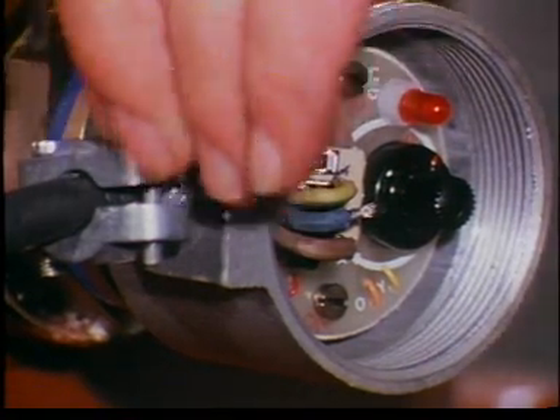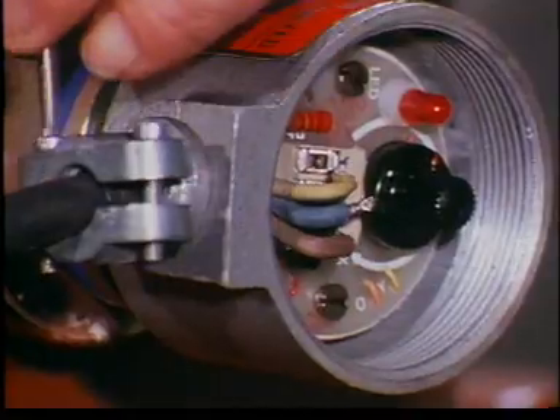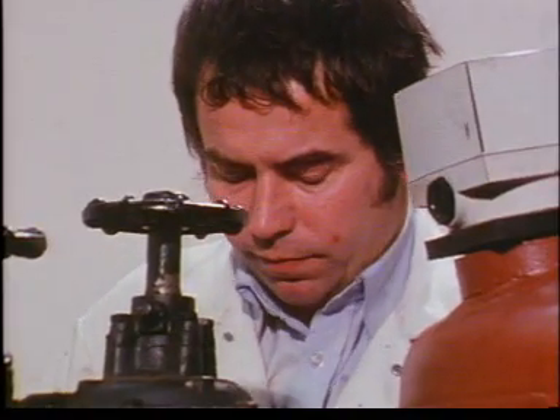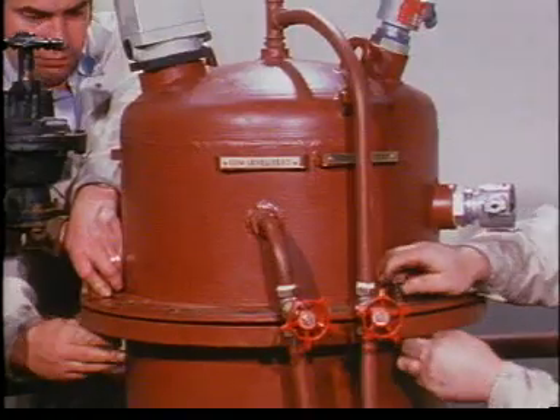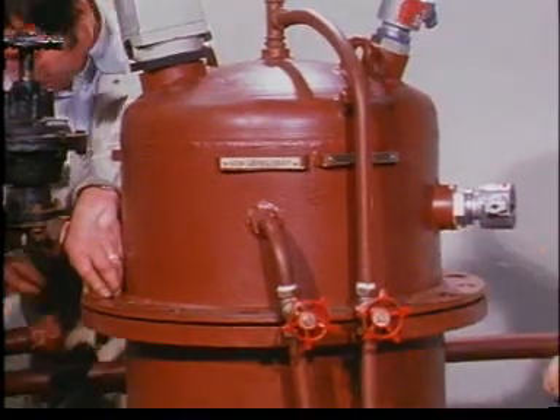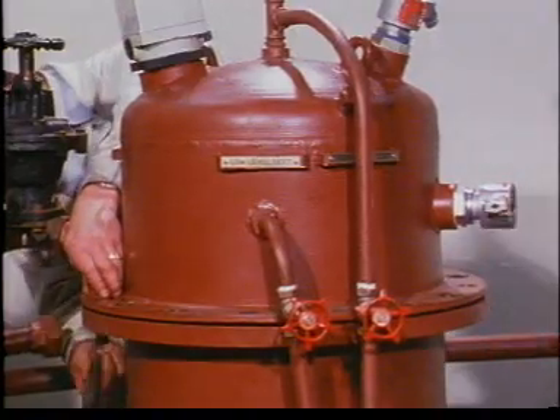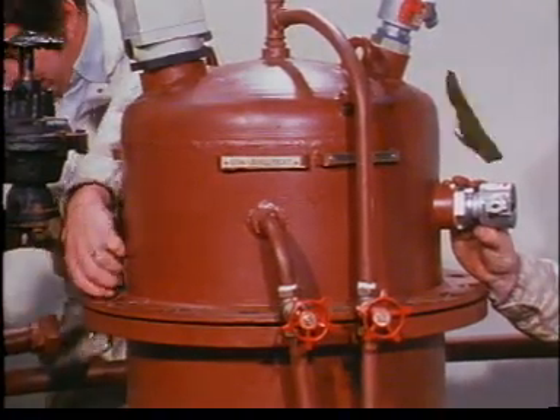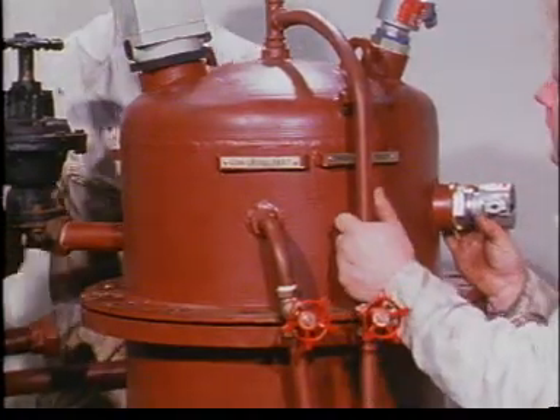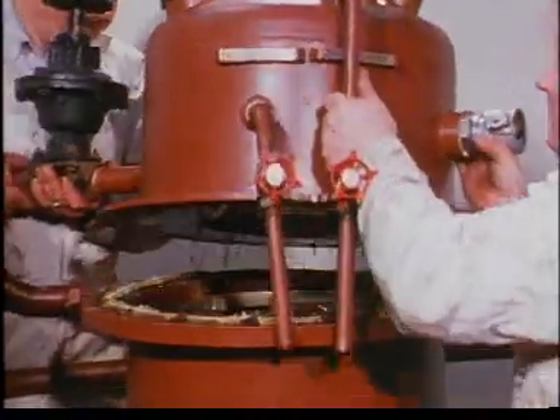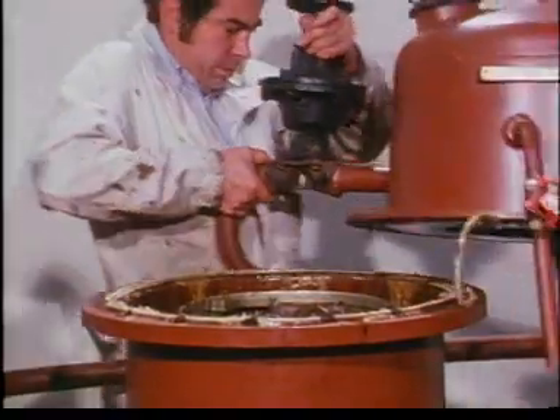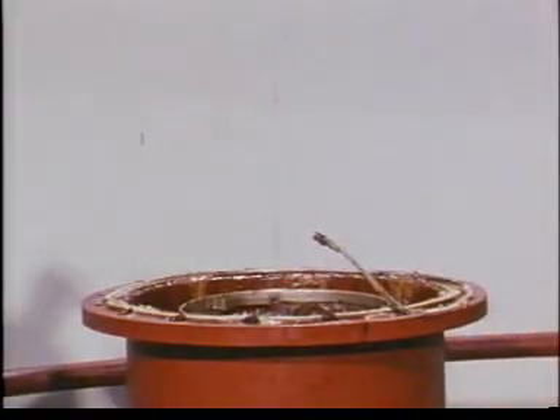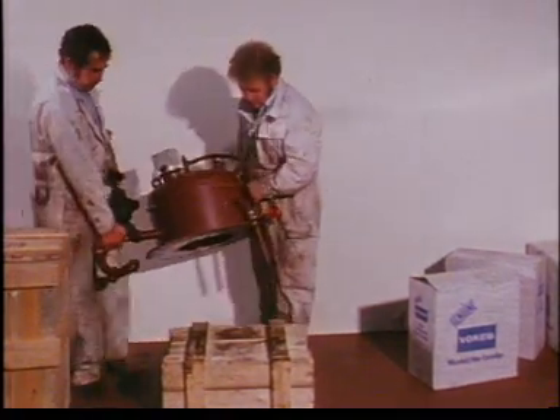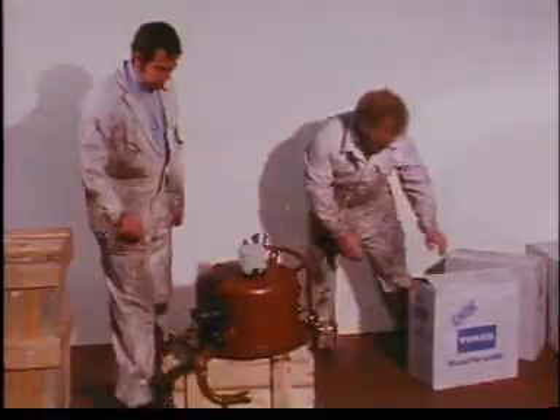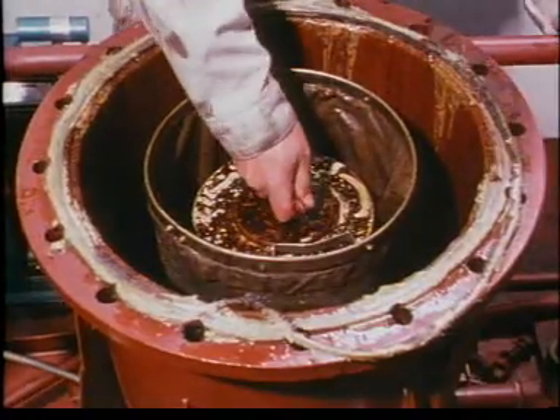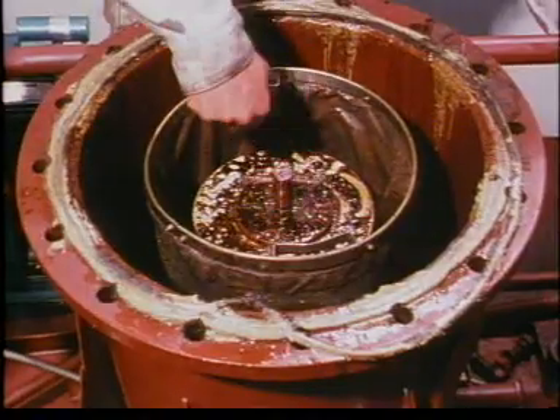The wiring and pipe connections to the top cover are disconnected. The top flange of the coalescer may now be unbolted. The dome can then be removed, which gives access to the coalescer elements. Finally, the coalescer elements can be removed by taking off the securing nut and element cap.